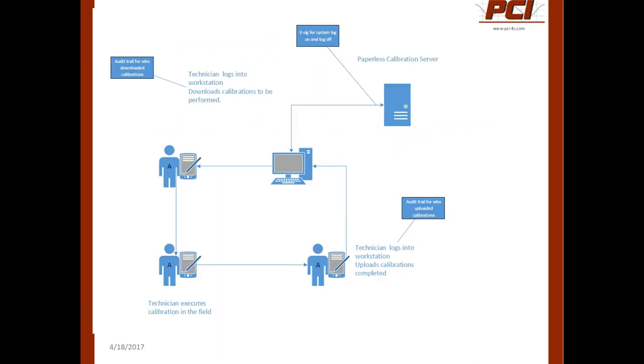One other thing we identified: if you look at this slide, you've got your paperless calibration server and a workstation. Individuals log in on the workstation, and that login generates an audit trail for when they logged in and were on the account. They would then download the calibrations to a handheld device, and the audit trail would show who downloaded which calibrations, and at what time.